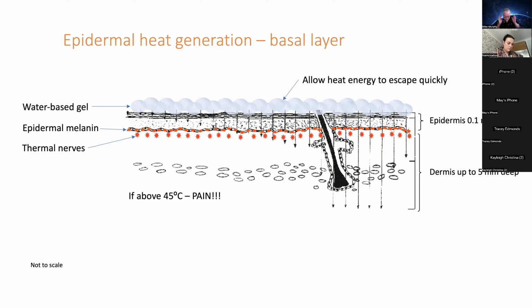Right. Okay. So you hit an interesting point there. You've got your fluence and your pulse width. Your fluence generates a certain amount of temperature, and the pulse width can determine the temperature as well. So you've got this balancing thing going on, right? The reality is there's a huge range of pulse widths and fluences that will work. It's not like it has to be that fluence and it has to be that pulse. No, it doesn't work like that. There's a huge range, and as long as you're in the right zone, then it should always work.